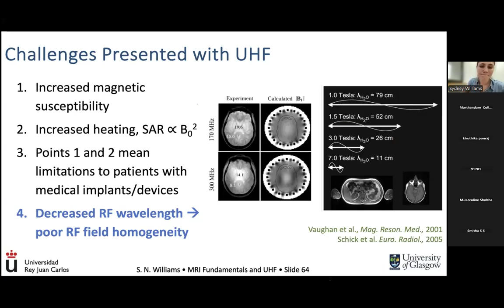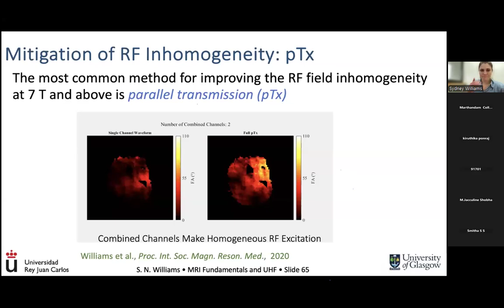The way that we can mitigate some of these problems is with something called parallel transmission. Essentially, it's the process of applying multiple transmit fields through a dedicated RF coil that allows us to shape the deposition of this radio frequency field in such a way that we can come back to a more uniform excitation and also mitigate the power deposition while we're doing it. This is just a nice GIF showing you 8 parallel transmit channels measured in vivo. These are radio frequency fields measured in Tesla per volt, but they have both magnitude and phase. When we put them together carefully, we can show each of their contributions, or in summation, where we'll generate a very uniform flip angle. The way that we do this is one of the really wonderful things that Shajan does himself: through dedicated parallel transmit coils, and they have a very unique hardware solution to independently generate these radio frequency fields.